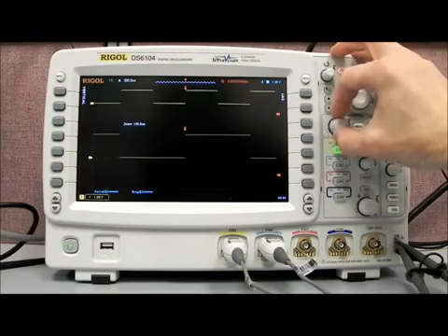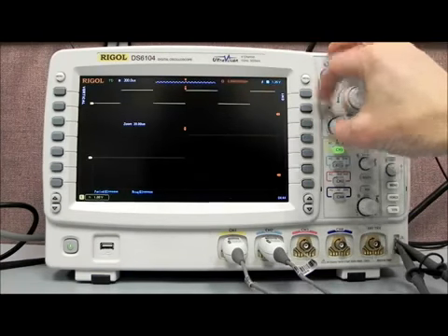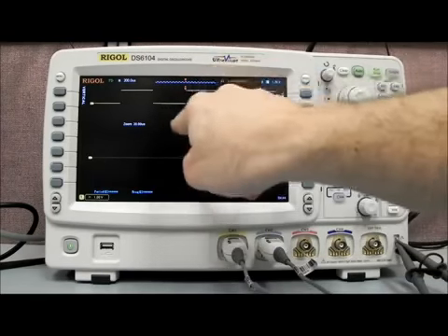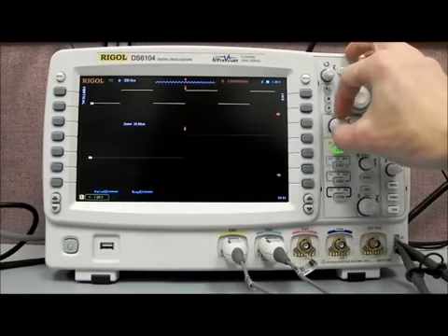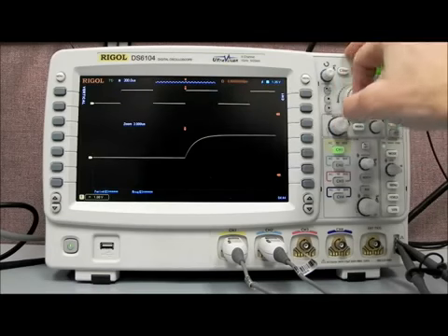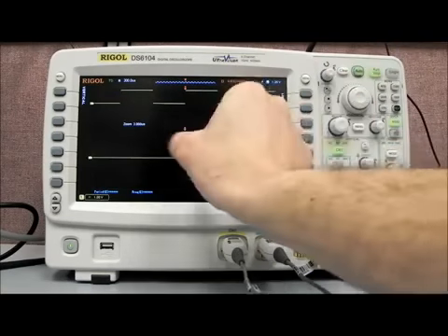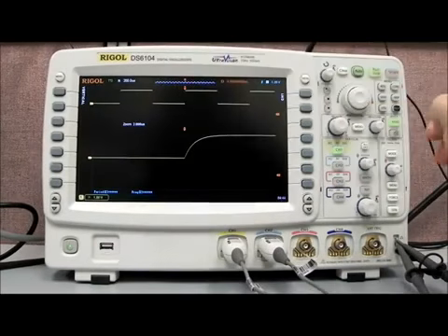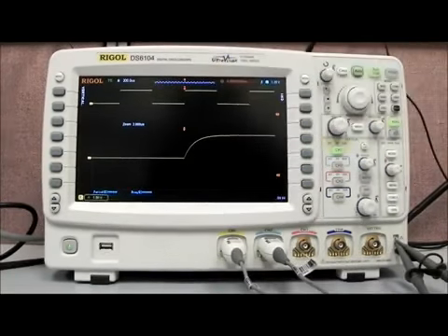Here what we can do is we're now in control of the bottommost screen. You'll see the window starts to shrink, so now the visible area that we have here is denoted by this black box on the top. And we can slowly make that larger, or smaller scale, so we're basically zooming in on this area of the display, or this original waveform that we have.